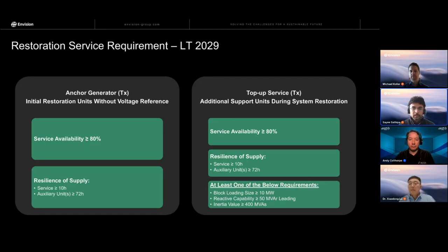So as part of the NESO technical requirements, there are two types of restoration services. One is the primary restoration service, which is the anchor generator, and the other one is a contractual top-up service. So what's the difference between an anchor generator and a top-up service? For the anchor generator, we are going to restore the system without any external voltage reference from the grid. Whereas on the top-up service, we are going to restore the system by taking the reference from an adjacent anchor generator or a power island system.